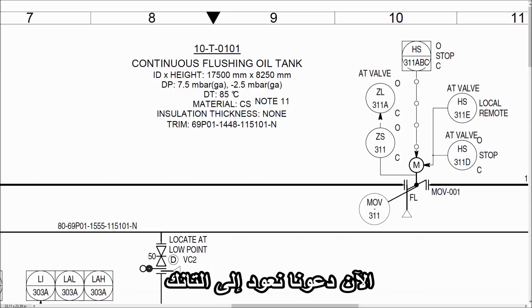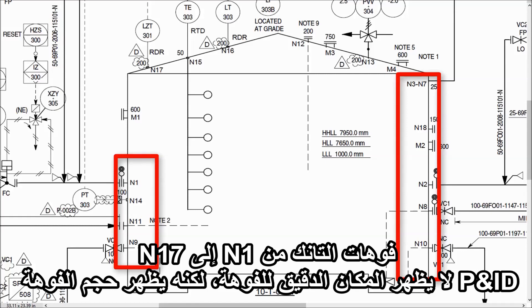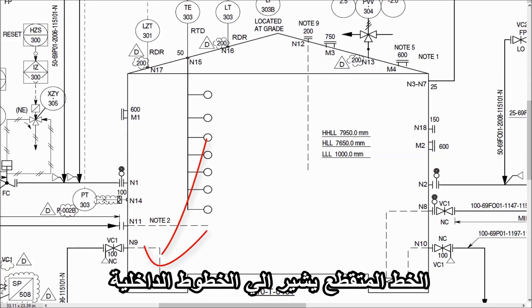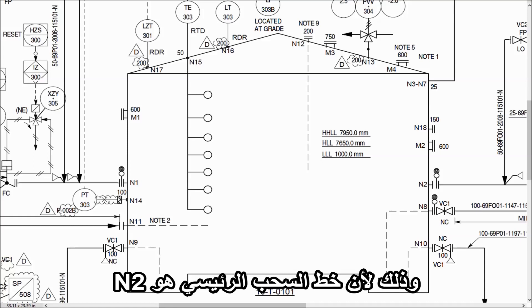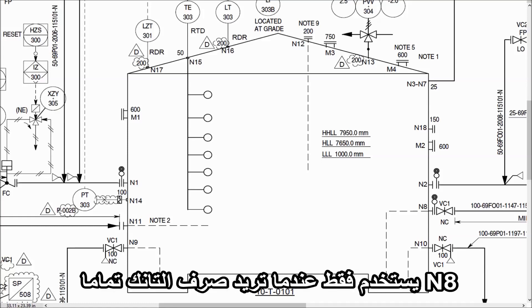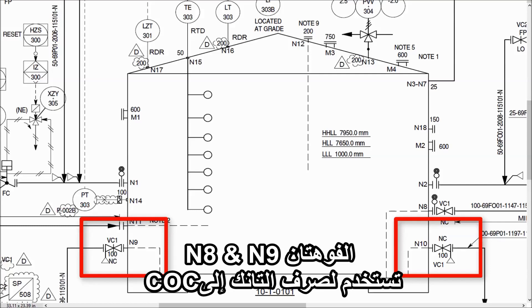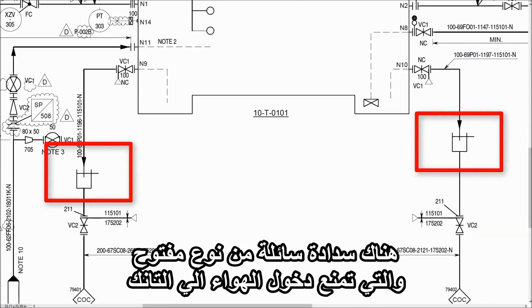Now let's go back to the tank. N1 to N17 are nozzle numbers. P&ID does not show the exact location of the nozzle, but it shows the size of the nozzle. Manholes are shown as M1 to M4. The broken line shows internal piping. There is a vortex breaker with nozzle N8 connected to the pump suction line with a normally closed gate valve — this is because the main suction line is N2, and N8 will be used only when you want to drain the tank completely. There are also nozzles N9 and N10 used to drain the tank to COC. This open type liquid seal prevents air ingress into the tank.